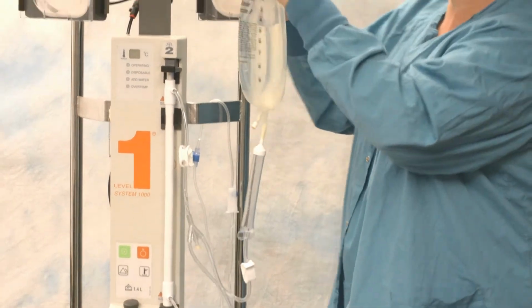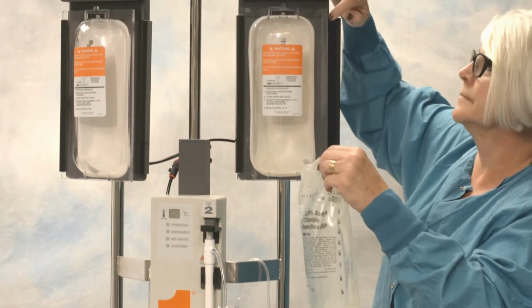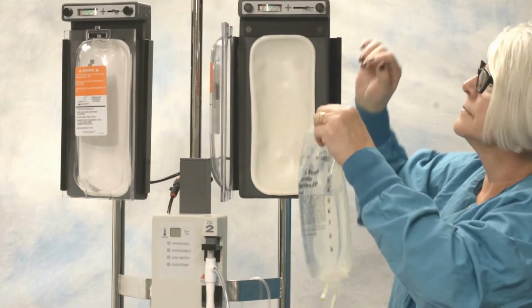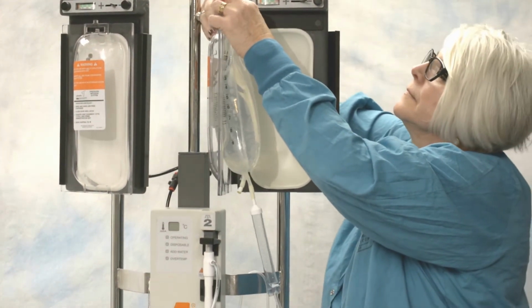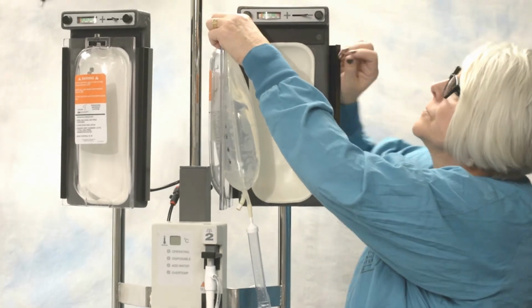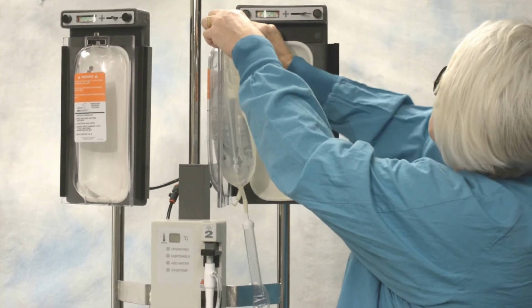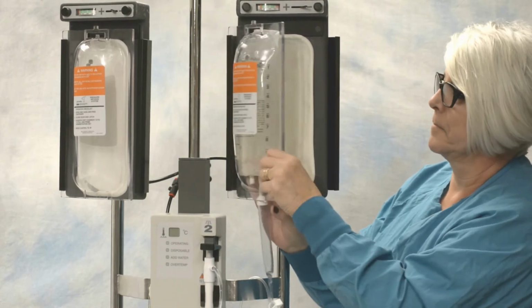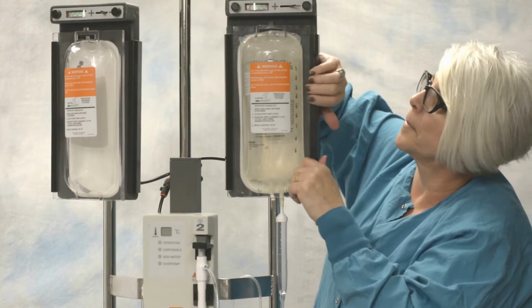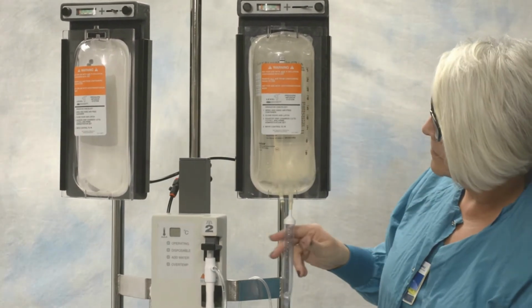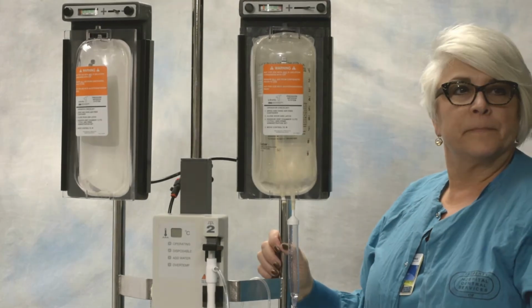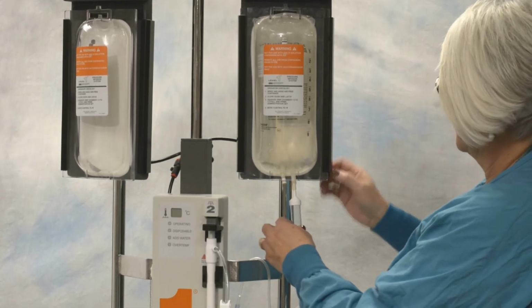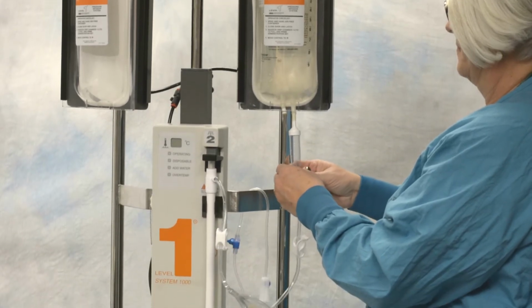After your bag is spiked, open the door of one of the 2 pressure compartments and hang your IV fluids from the hook at the top of the door. Gently close the door. It should close easily around the valves at the bottom. Then squeeze the drip chamber until your drip chamber is about 3/4 of the way full.